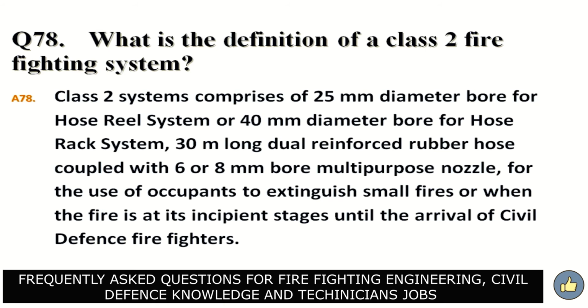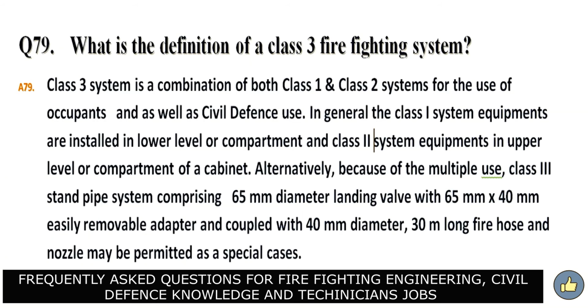of civil defense firefighters. What is the definition of Class 3 firefighting system? Answer. Class 3 system is a combination of both Class 1 and Class 2 system for the use of occupants as well as civil defense use. In general, the Class 1 system equipments are installed in lower level or compartment and Class 2 system equipments in upper level or compartment of a cabinet.